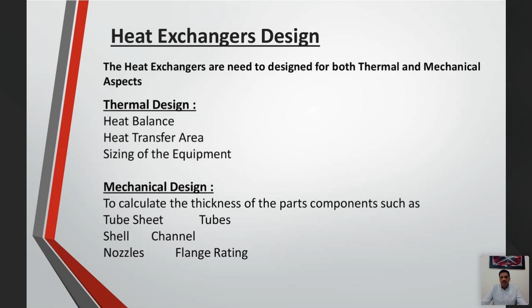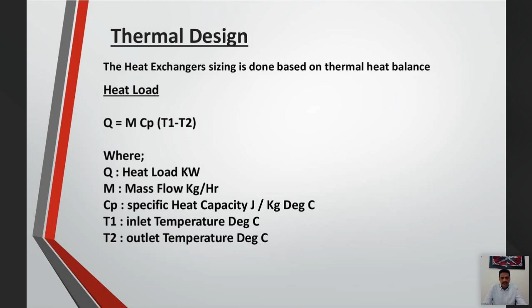When we look into the thermal design, as I told you earlier, you have to do a heat load calculation. Heat load calculation is a very simple formula, which is the same formula every time. Q equal to m Cp delta T, or T1 minus T2, or you can say temperature difference, where Q is the heat load, m is the mass flow, Cp is the specific heat, and T1, T2 are the inlet and outlet temperatures. From here, you will find out how much heat load is required.